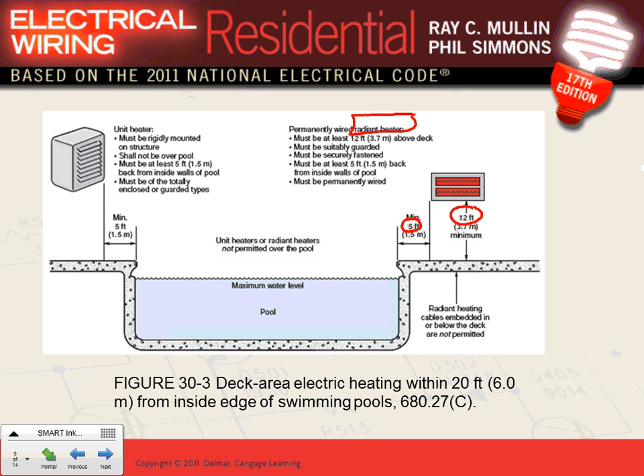So now if you have a unit heater that has a fan in it, a heating element and a fan, the heating element could be electric, or it could be gas. A radiant heater could also have gas as the heating element and you're just blowing a fan through it. Does that make sense? If you have that one, here's the limitation. Your limitation is only 5 feet. There's no limitation on how far, because all you're doing is blowing air through a heating coil, which could most likely be gas. You're burning gas and blowing air through this coil. So they allow you 5 feet. So there are a lot of requirements for this one, guys.